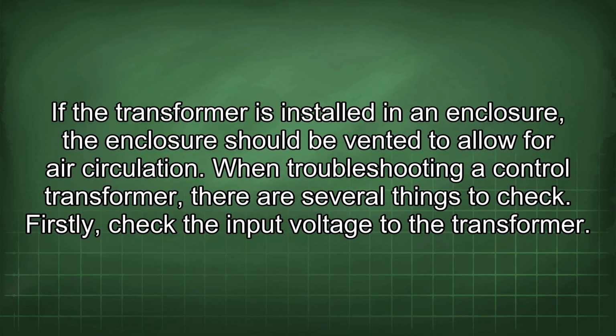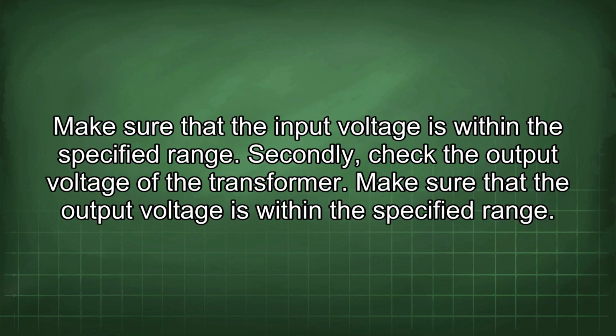When troubleshooting a control transformer, there are several things to check. Firstly, check the input voltage to the transformer. Make sure that the input voltage is within the specified range. Secondly, check the output voltage of the transformer. Make sure that the output voltage is within the specified range.